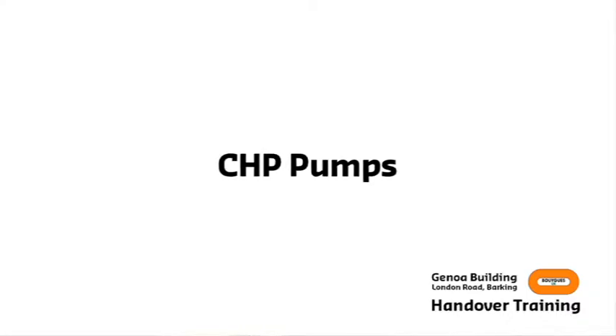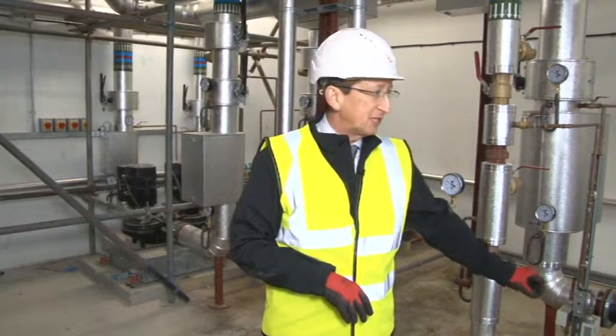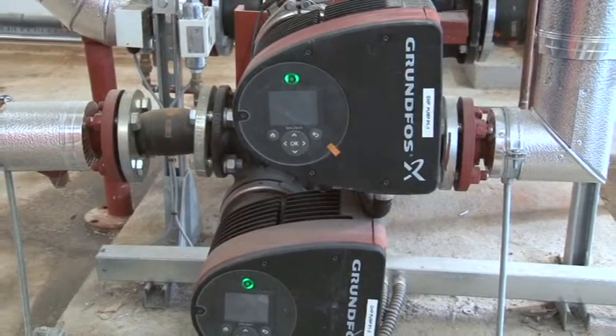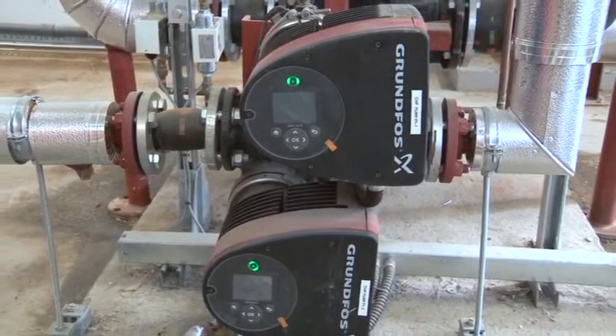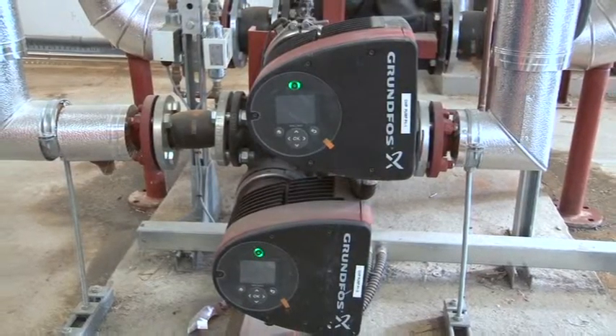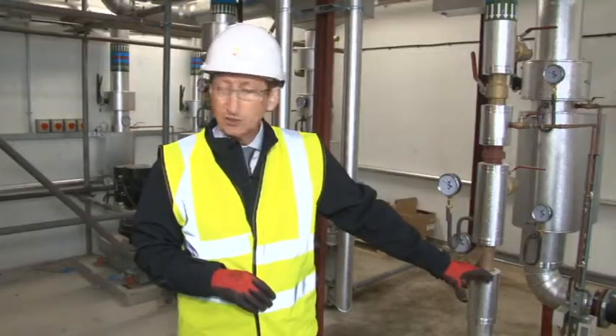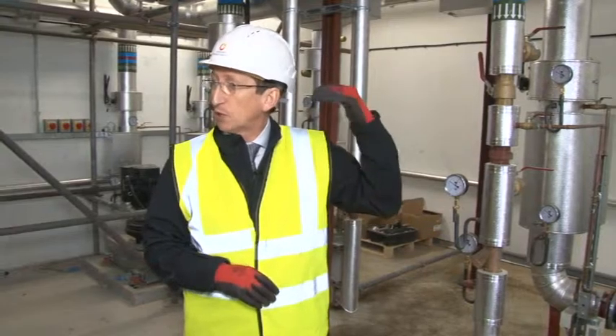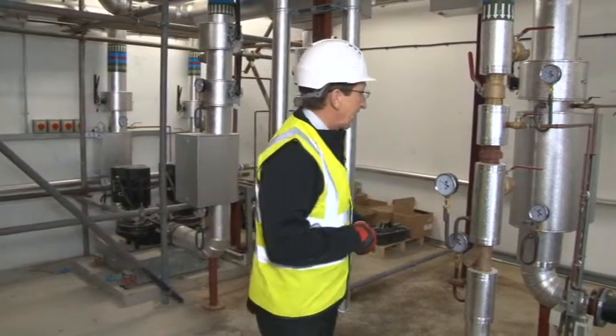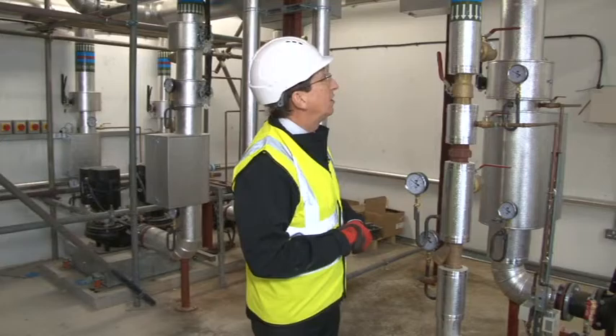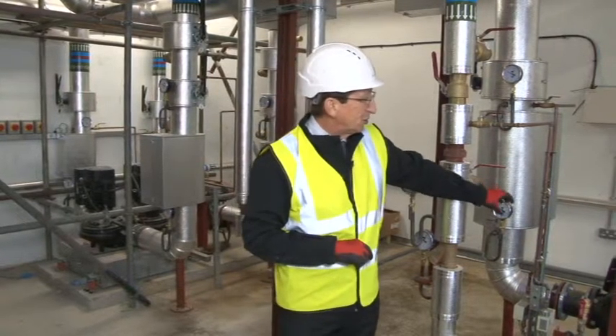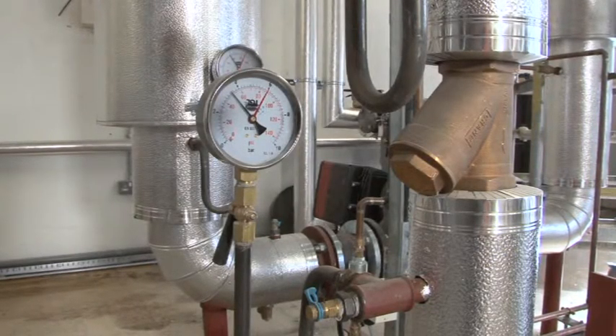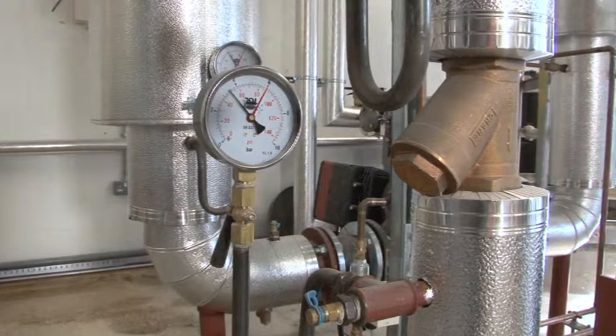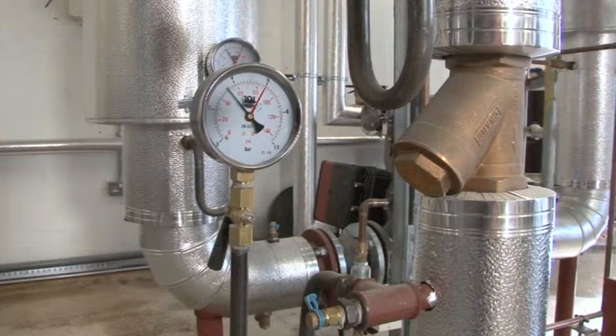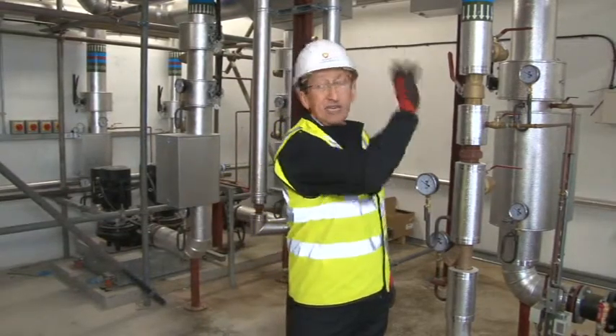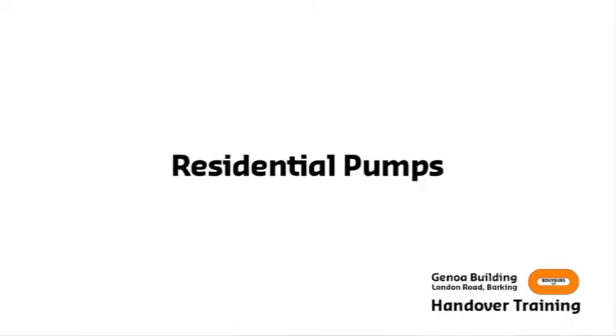Okay, so the pump sets here, this set of pumps right in front of us are pulling the water out of the CHP thermal store and supplying that into the system. So the header pipe work above us. So that's what those pumps are doing, pulling it out from the CHP and supplying it into the system. The ones on the far side are circulating the water from the boilers into the header of the system as well. So there's a circulation of the primary round from the boilers and up into the header pipe work itself. Okay.